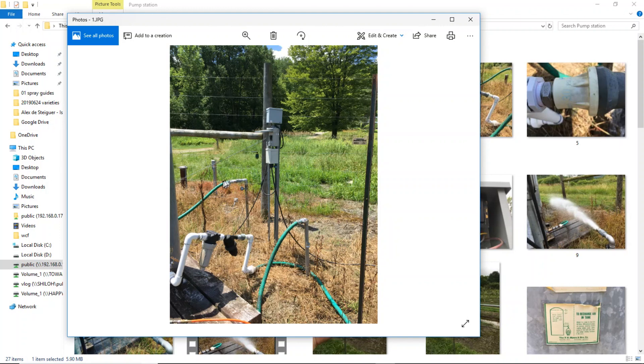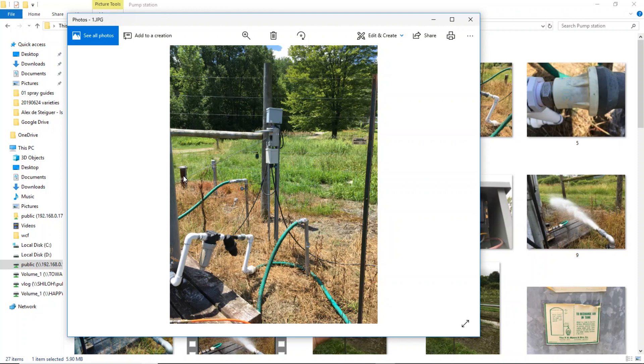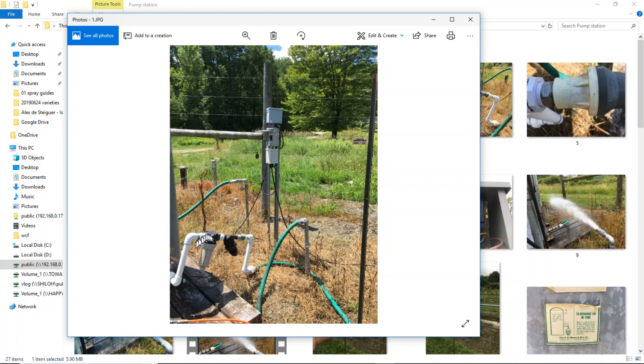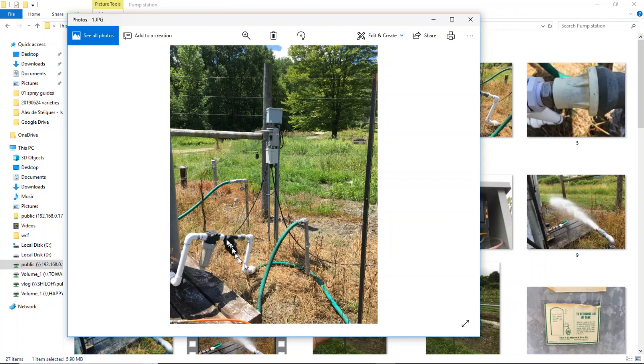The water comes out and goes through a flow rate regulator that provides back pressure to the pump. It's a very shallow pump. Our water is within five feet of the surface, so I have very little head on it. That keeps me from over-speeding the motor on the electric pump. That water flows through a gate valve, a one-way check valve into the volume tank. Outflow is controlled by the gate valve. It goes through progressive screens—a coarse screen and a fine screen. I believe this is a 100 and this one's a 50. These are made by Toro. All of this plumbing is inch and a quarter.